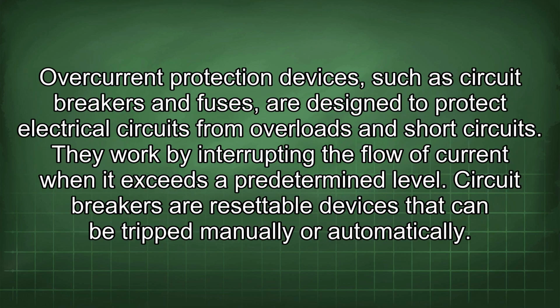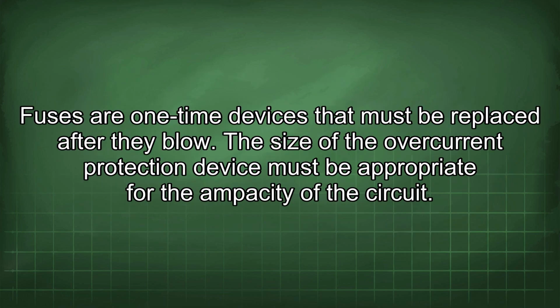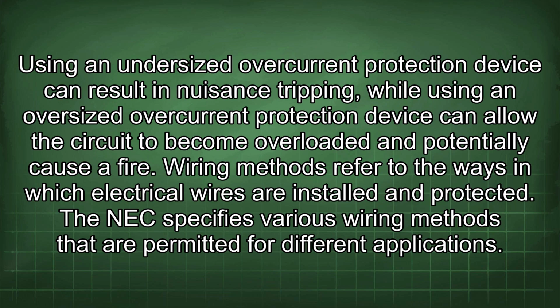Overcurrent protection devices, such as circuit breakers and fuses, are designed to protect electrical circuits from overloads and short circuits. They work by interrupting the flow of current when it exceeds a predetermined level. Circuit breakers are resettable devices that can be tripped manually or automatically. Fuses are one-time devices that must be replaced after they blow. The size of the overcurrent protection device must be appropriate for the ampacity of the circuit. Using an undersized overcurrent protection device can result in nuisance tripping, while using an oversized overcurrent protection device can allow the circuit to become overloaded and potentially cause a fire.